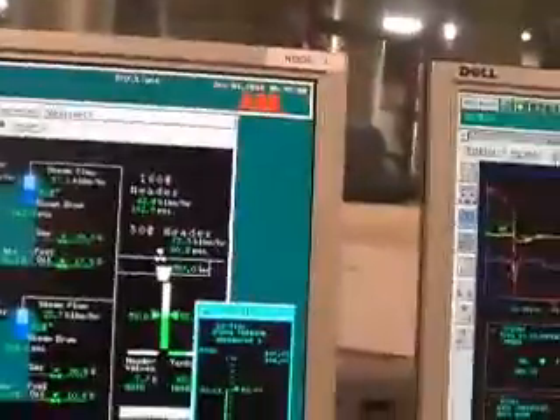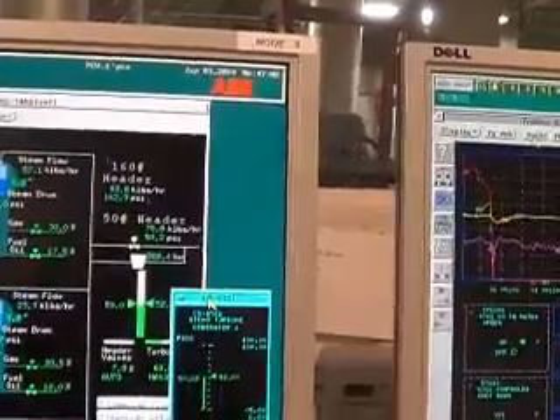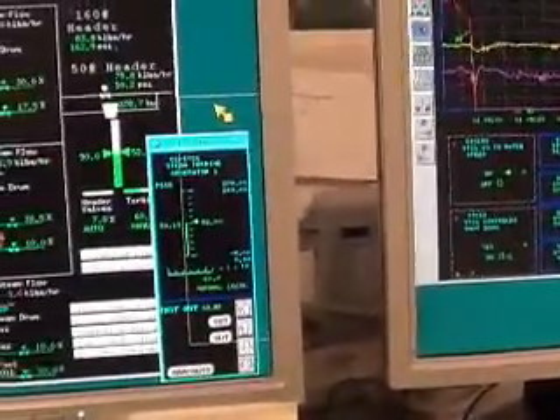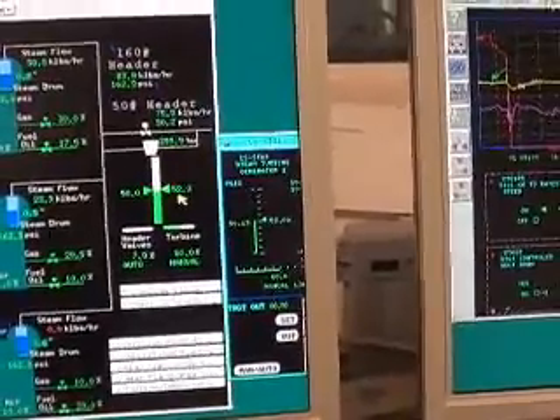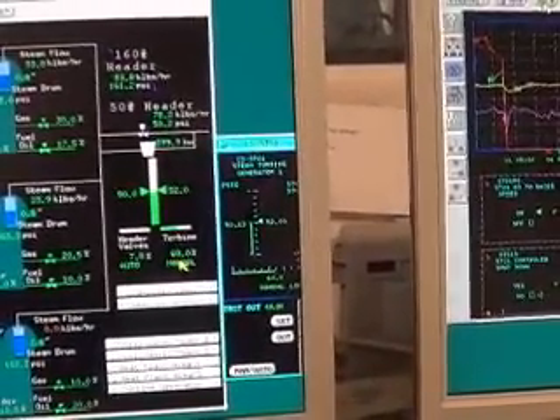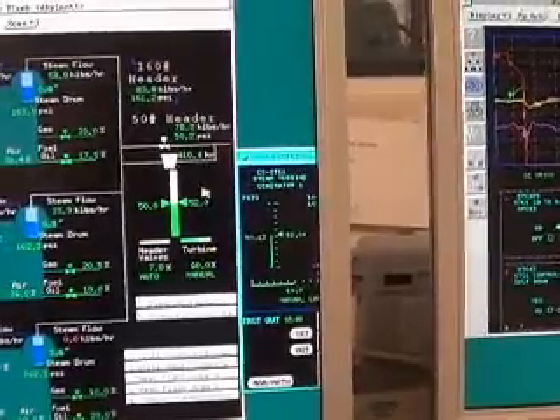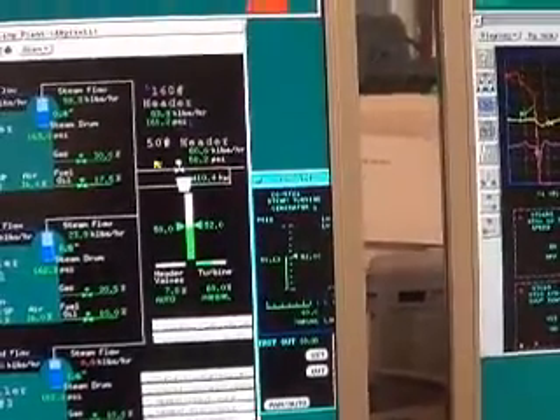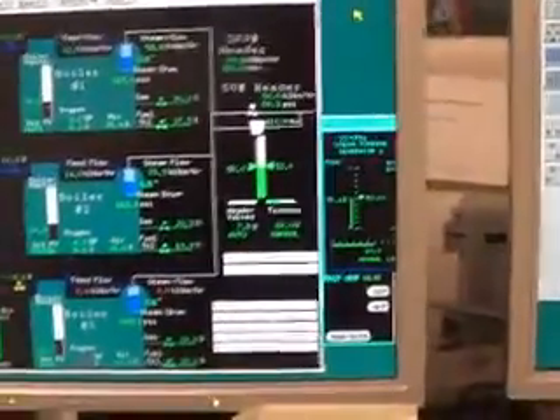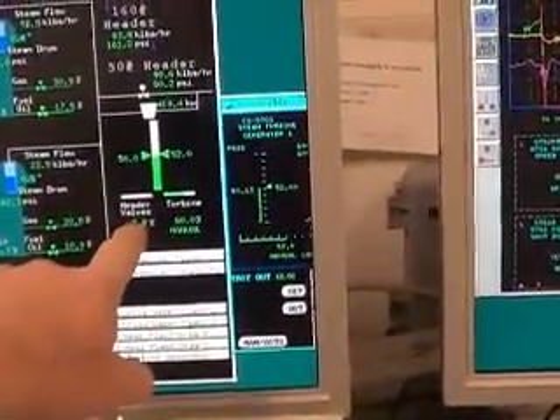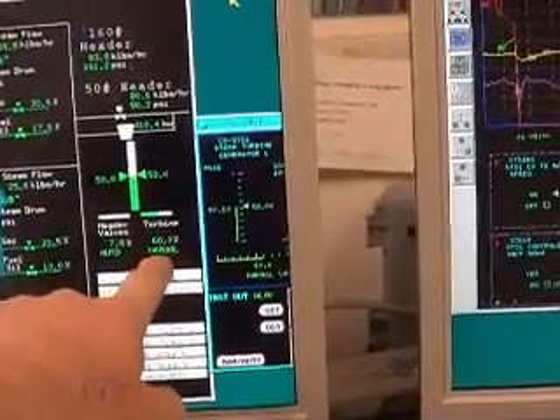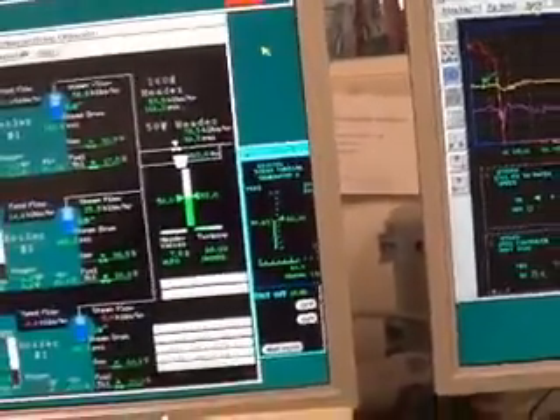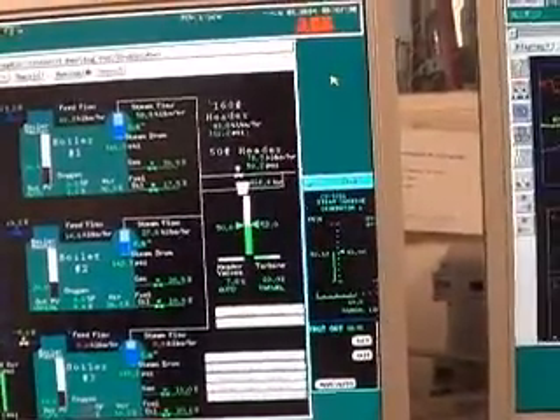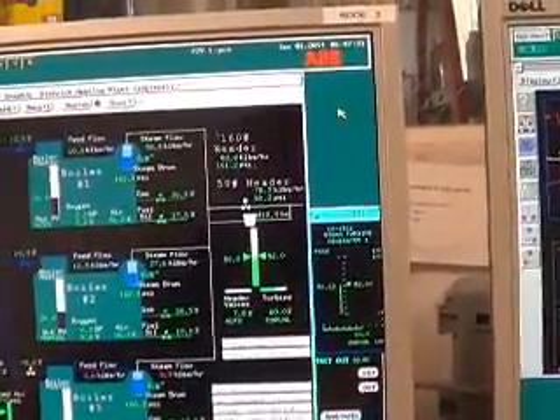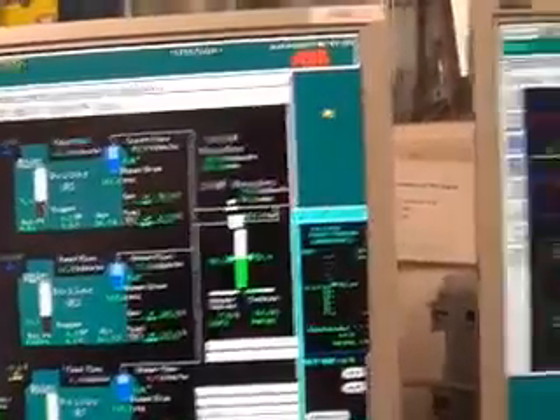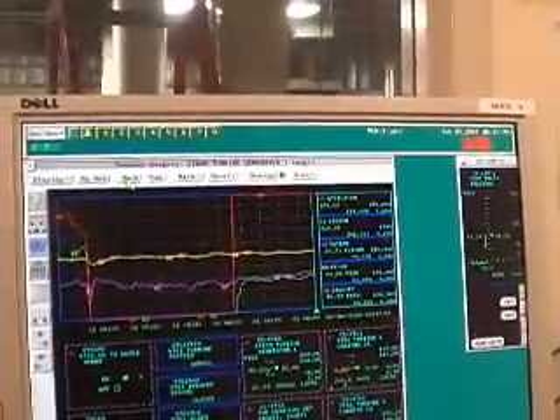So what we're doing here is getting this turbine. It's in manual. We're going to gradually bring it up to 100%. Doesn't make that much difference on the steam coming out of the boilers. It just makes a difference whether it's going through a regulating valve or it's using the exhaust off the turbine. When you're at 100%, you're making the most electricity that you can make for a given load. That's how that works. And we can see our trend log is still going.